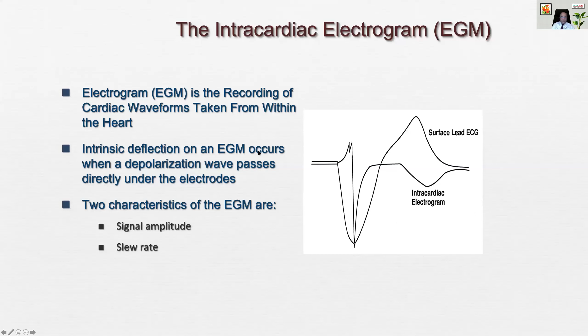Third one was a spontaneous QRS, but not sensed. Now, this may have been in the refractory period, so it doesn't matter. Sometimes after any sensed or paced event, there is a period which we call the refractory period where the pacemaker stops sensing. So this may be in the refractory period, but it's obviously not sensed. And then the next one is again not sensed, and the pacemaker gives a spike. So the pacemaker is not sensing. This is called undersensing.